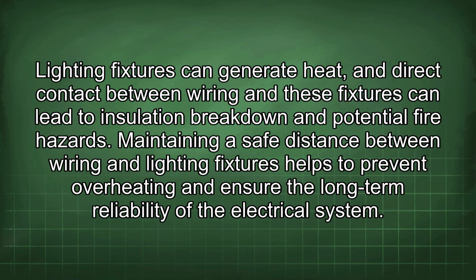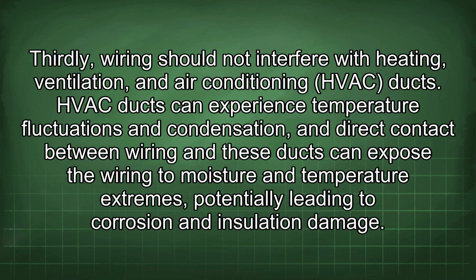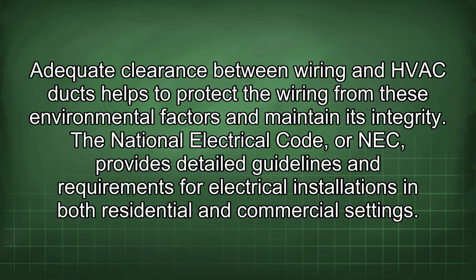Lighting fixtures can generate heat, and direct contact between wiring and these fixtures can lead to insulation breakdown and potential fire hazards. Maintaining a safe distance between wiring and lighting fixtures helps to prevent overheating and ensure the long-term reliability of the electrical system. Thirdly, wiring should not interfere with heating, ventilation, and air conditioning (HVAC) ducts. HVAC ducts can experience temperature fluctuations and condensation, and direct contact between wiring and these ducts can expose the wiring to moisture and temperature extremes, potentially leading to corrosion and insulation damage. Adequate clearance between wiring and HVAC ducts helps to protect the wiring from these environmental factors and maintain its integrity.